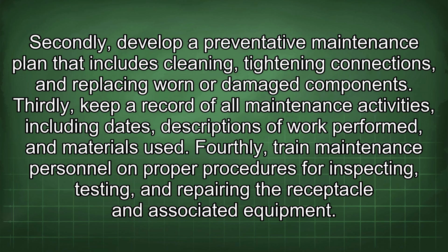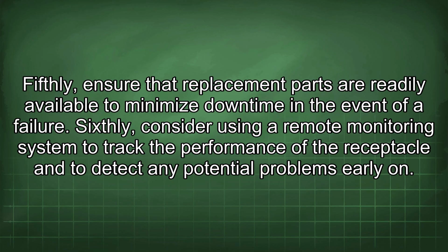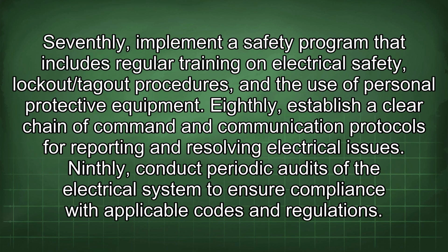Thirdly, keep a record of all maintenance activities, including dates, descriptions of work performed, and materials used. Fourthly, train maintenance personnel on proper procedures for inspecting, testing, and repairing the receptacle and associated equipment. Fifthly, ensure that replacement parts are readily available to minimize downtime in the event of a failure. Sixthly, consider using a remote monitoring system to track the performance of the receptacle and to detect any potential problems early on.